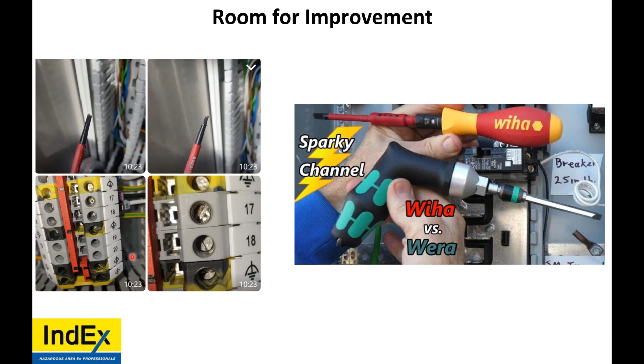Now when we look at rooms for improvement, take a look on the left here. This terminal was too tight, so it broke the screwdriver - the termination was incorrect. A tool exists within the industry for how you're supposed to tighten terminals, a torque screwdriver. That's good change management, implementing a good quality management system by using the correct tools. If the vendor, manufacturer, EPC, or end user provided their workers with the correct tools, things like this would be lessened.